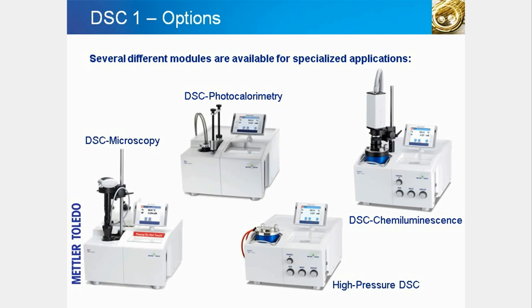DSC chemiluminescence allows you to detect the light emitted by a chemical reaction — for example, the chemiluminescence originating from oxidative degradation processes in polymers. This allows you to study the effect of stabilizers in polymers. In the food and pharmaceutical industries, chemiluminescence is used to obtain information about the stability of various products such as oils or fats.